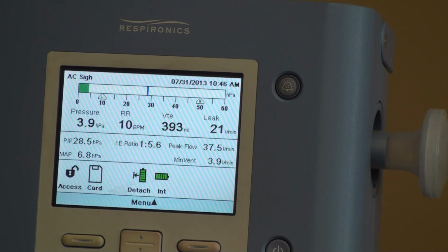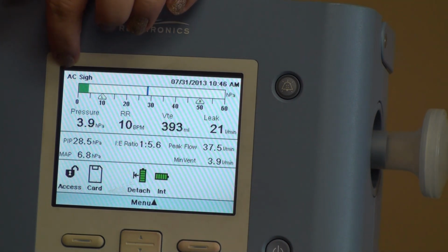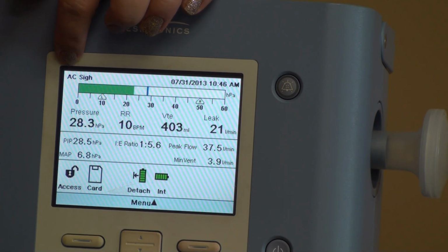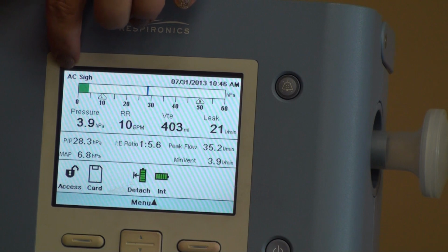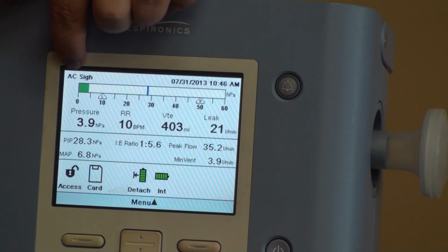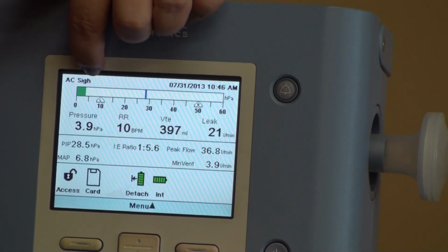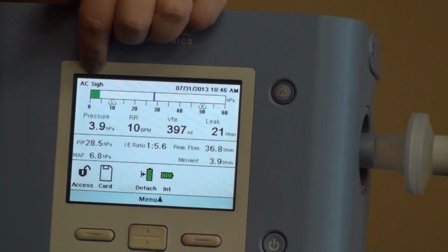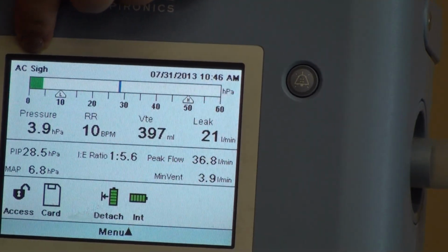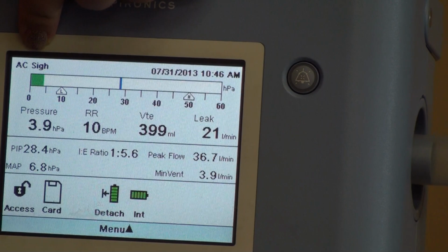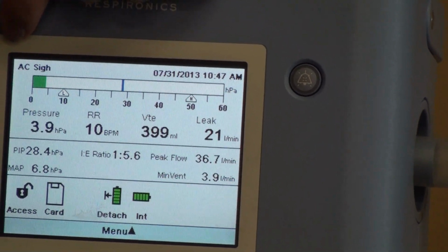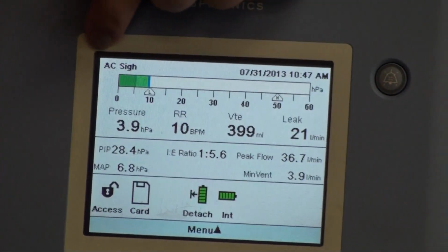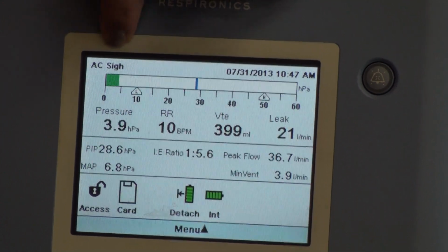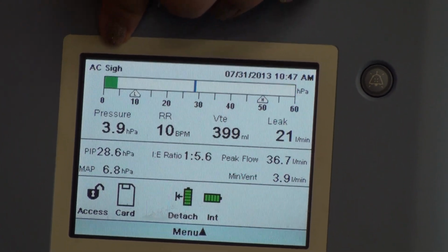The therapy mode is going to be right next to it here, and there's several different therapy modes in here. Right now I have it on assist control, so it says AC, and it has the word Sigh back behind there. The only reason it has the word Sigh on there is because I have the Sigh feature turned on. If it was not ordered and I did not have it turned on, it would just say my mode, which would be assist control, SIMV, CPAP, or whatever it might be with this particular ventilator or client.